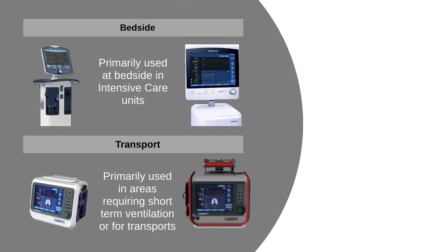In this lecture, we will differentiate between two types of ventilators. The first one is the bedside ventilator, which is primarily used in the ICU setting at the bedside. These ventilators are not built for transport because they usually do not have adequate battery life to achieve transportation. On the left is the Puritan Bennett 980 ventilator, and on the right is the Hamilton G5 ventilator.